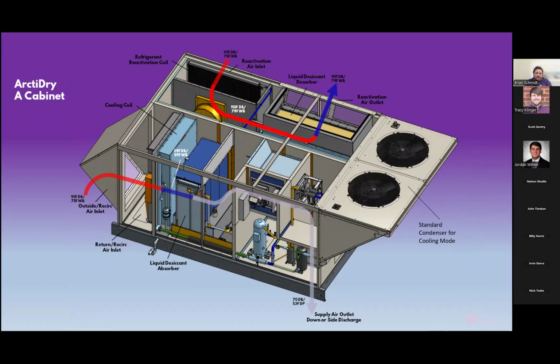As you can see on the far left, at the bottom, we have outside air coming in. We do have that return air inlet, if you would like to use some return air. But outside air is coming in. First thing it's going to do is pass through our filter bank. This is a 2 and a 4-inch filter bank, MERV 8, MERV 13. It's then going to pass through a 4-row coil. We don't have 6-row coils or 5-row coils. We're using a 4-row coil because we're not getting the vast majority of our dehumidification through our cooling coil, but we are getting some. So there is a little drain you'll see down there at the bottom of the coil.